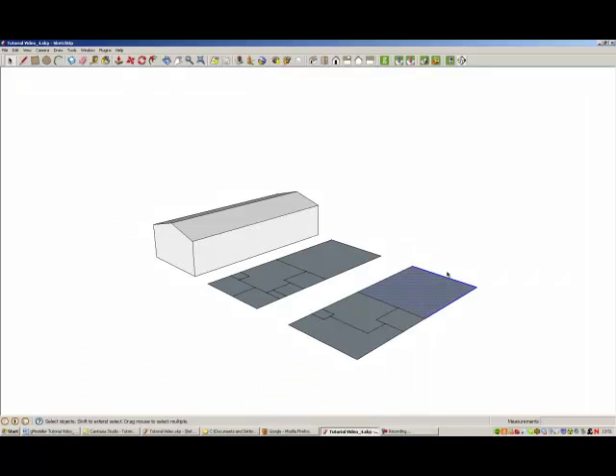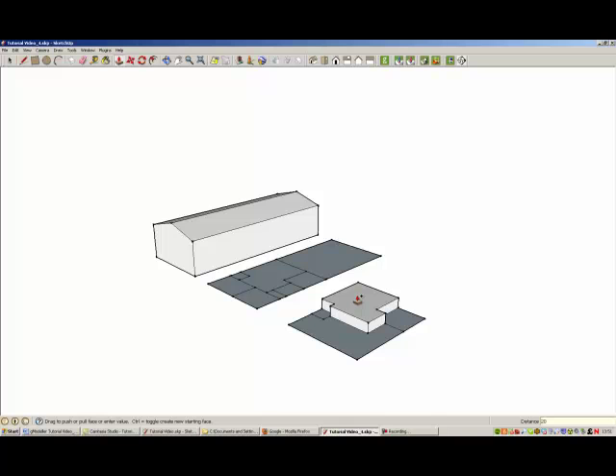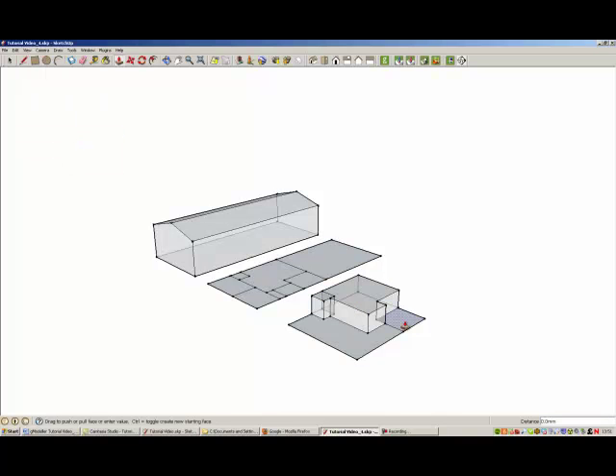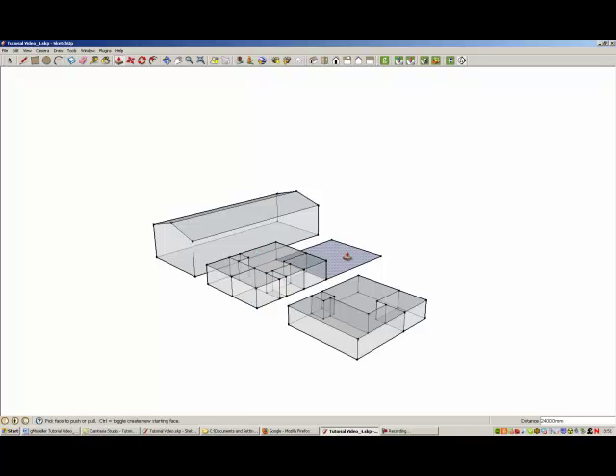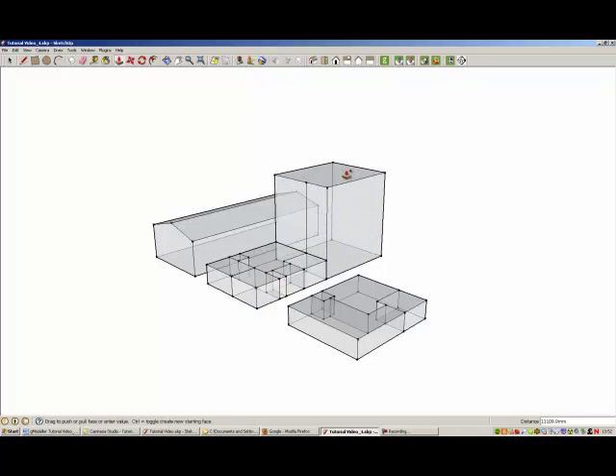I will now begin to model my internal zones by extruding the surfaces of my floor plans. The height at which I extrude these is the floor-to-floor heights present in my building. When I click on a surface of my floor plan to extrude it, I press Control on my keyboard, which extrudes that surface as a separate entity. By doing this, the internal walls are generated automatically, eliminating the need to draw them manually using the line tool, thus saving a lot of time — particularly when modelling larger building models.